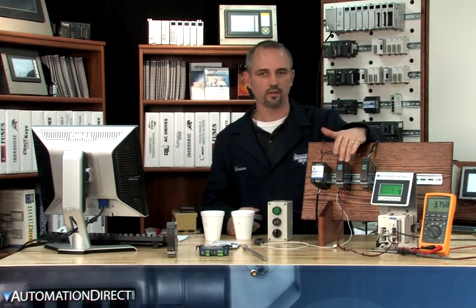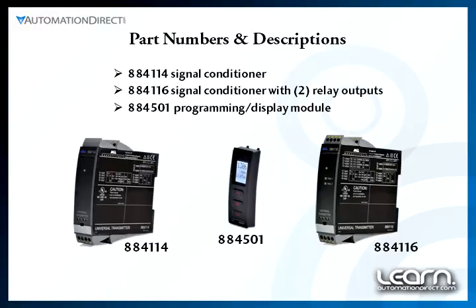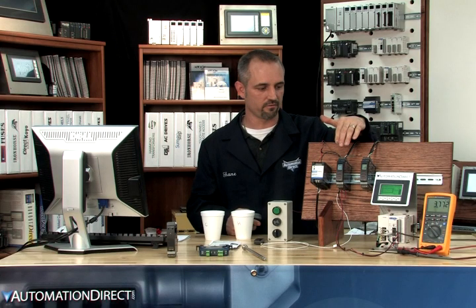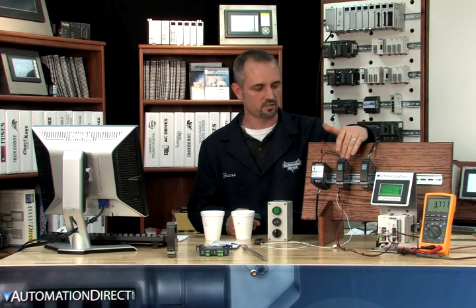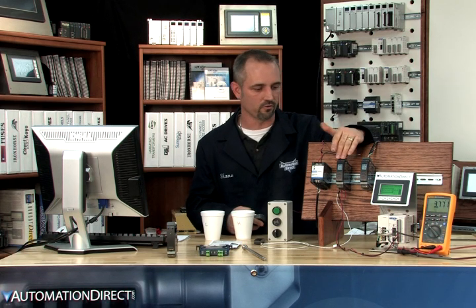We have set up the signal conditioner to convert one signal — which is our RTD — to a new signal, 1 to 5 volts. There are settings in the signal conditioner that will have to be programmed. We will cover how to program the conditioners in the next video, but for now we're going to show why and where you would use a signal conditioner. We have two models: one with a relay contact output, which is what we're going to use today, and the other is a non-relay type output. The converted signals inside both are the same — the difference is one has a relay and the other does not.